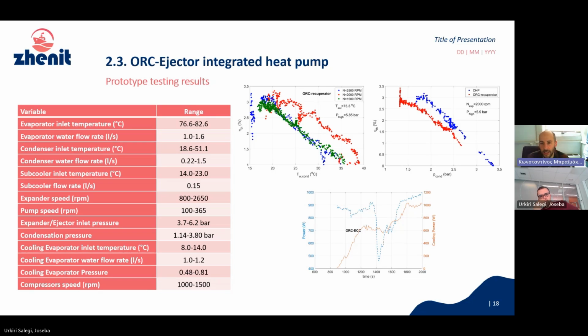In the top left diagram, you can see some results that are related to the electricity only mode. So in this case, we just have the ORC with a recuperator. And the tests refer to cooling water temperatures at the condenser of the system between 15 to 40 degrees. Under these conditions, we have a maximum pressure of the ORC at 5.85 bars. And we know from theory, and this was also verified from the experiments, that increasing the cooling water temperature led to a reduction of the thermal efficiency. Overall, the thermal efficiency ranged from a maximum of about 3% at the lowest temperature to about 1% when we raise the temperature to 35 to 40 degrees.